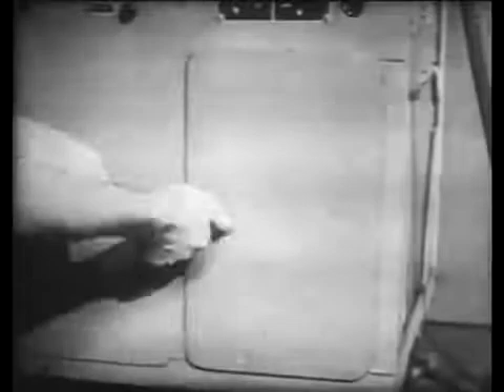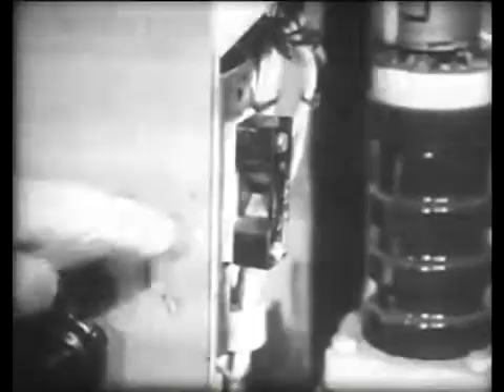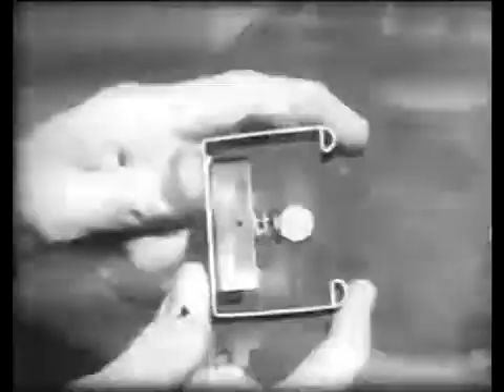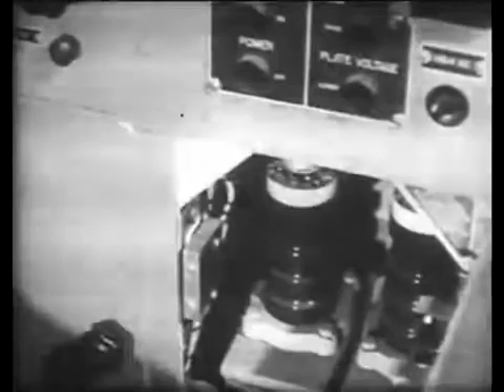In the doors and panels of some equipment, interlocks are installed as safety devices. When the door or panel is opened, the interlock automatically breaks the power circuit. When the equipment must be worked on while live, a special clip, and only a special clip, should be plugged into the interlock to keep the circuit energized. This special clip is so designed that the door will not close until it is removed.